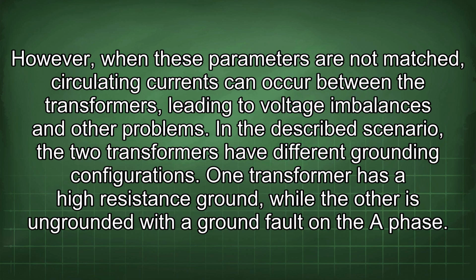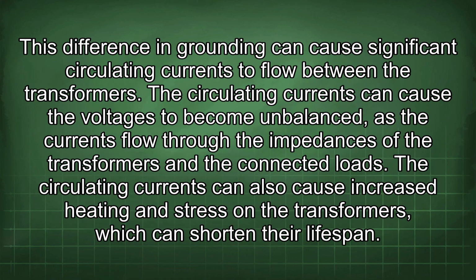One transformer has a high resistance ground, while the other is ungrounded with a ground fault on the A phase. This difference in grounding can cause significant circulating currents to flow between the transformers. The circulating currents can cause the voltages to become unbalanced as the currents flow through the impedances of the transformers and the connected loads.